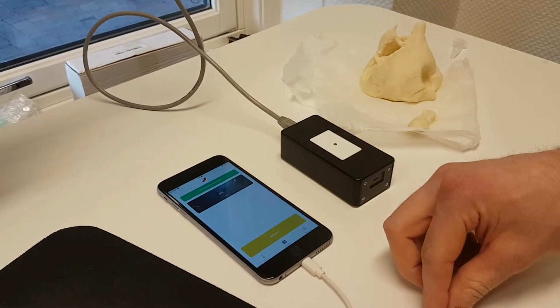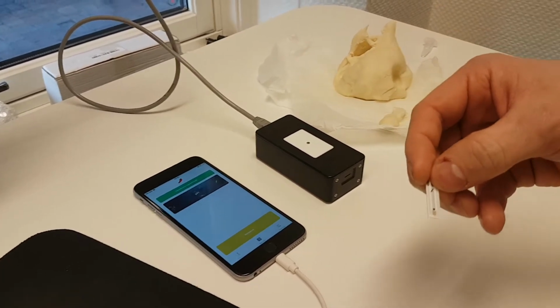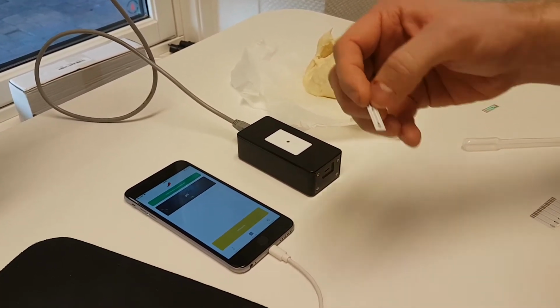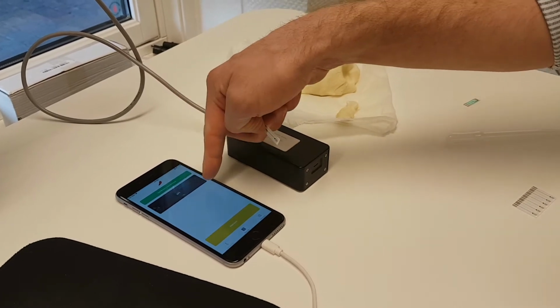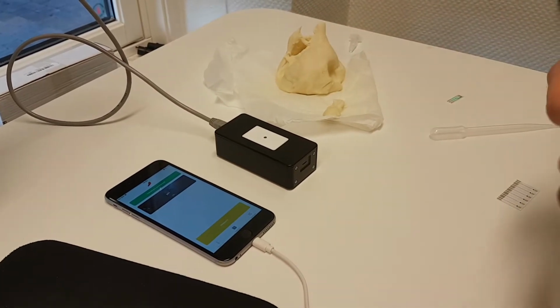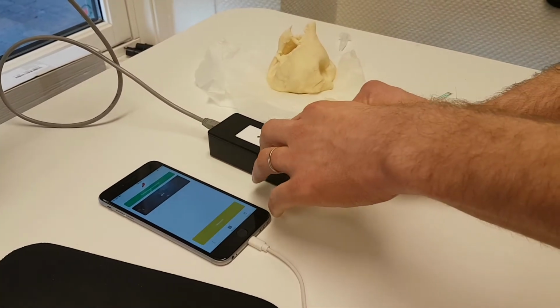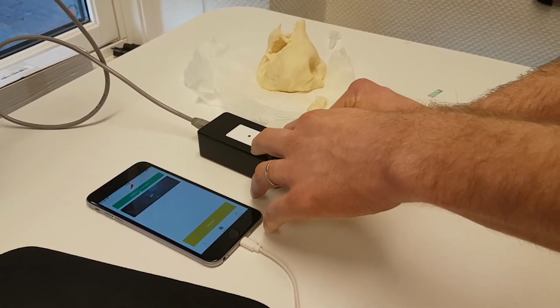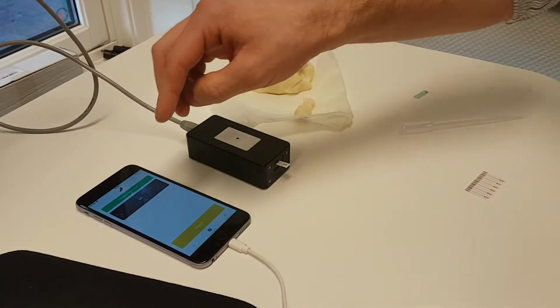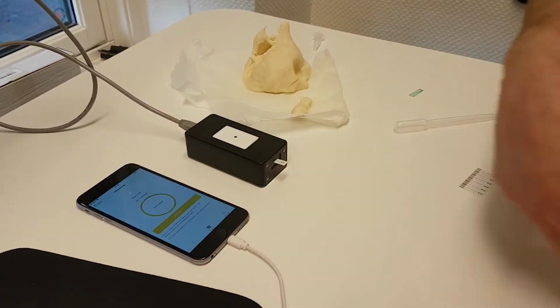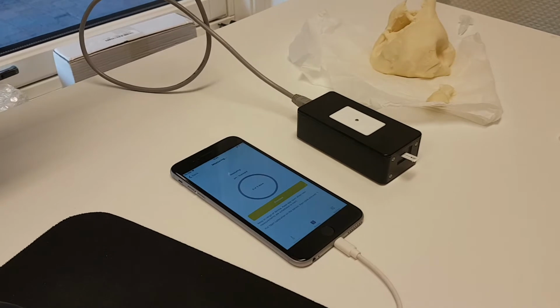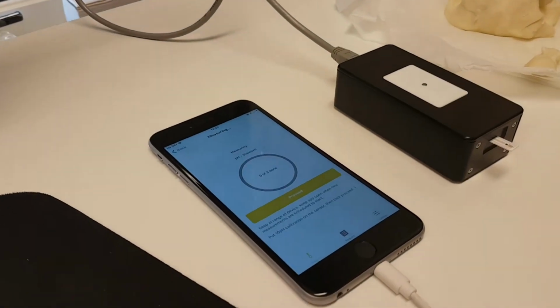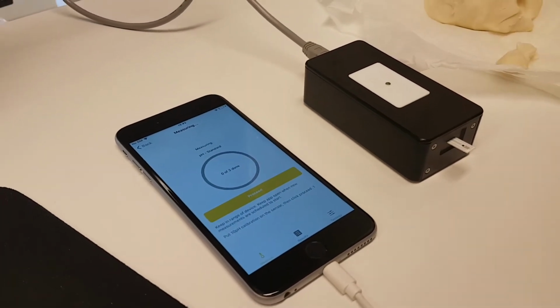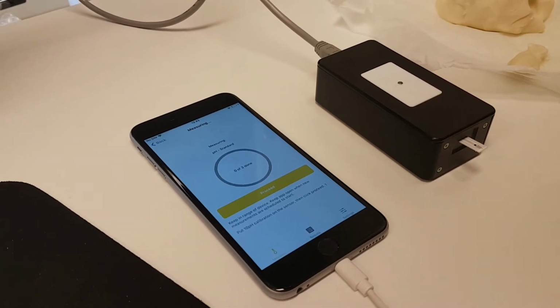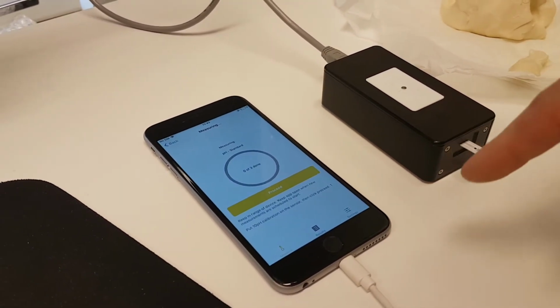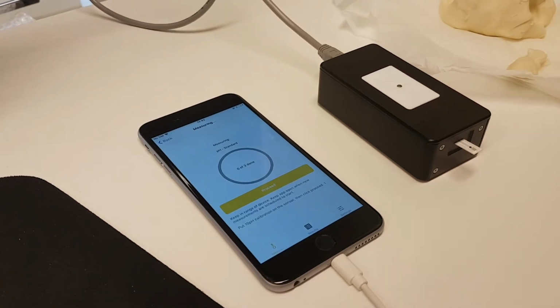So we're going to use our 2-point calibration pH sensor. It looks like this. We're going to choose pH on the app, and then we'll just stick the sensor into our meter and hit measure. Now when we do that, it's going to give us a set of instructions. It might be a bit difficult to see in this camera angle, but what it says is to put pH 10 calibration solution on the sensor and then proceed.